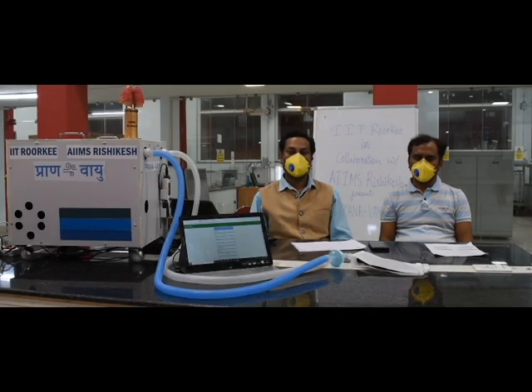Let me tell you the special features of this Pranvayu ventilator, which is a portable type mechanical ventilator. In this ventilator, we have achieved several modes, and these modes are tidal volume controlled and pressure controlled. So let me start with the very basic mode, which is required for COVID-19 patients. When the patients are completely sedated and cannot take their own breath, we usually give our first mode, which is controlled mechanical ventilation, CMV. This CMV can be of two types, which can achieve certain tidal volume and it can also achieve certain pressure. So based on that, we have CMV-P and CMV-V versions.